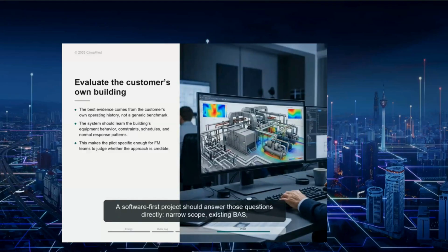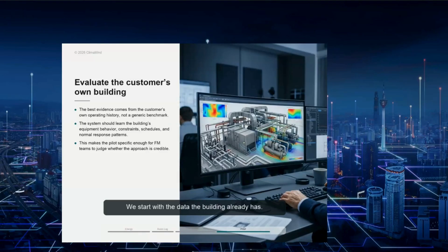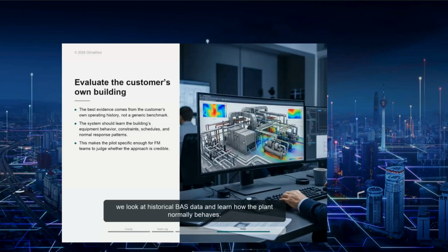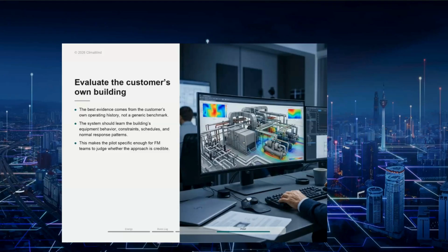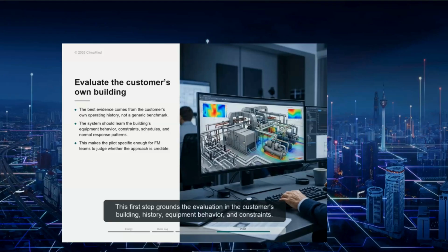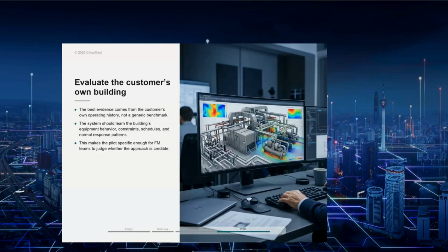Narrow scope, existing BAS, approved points and ranges, lighter installation, low tens of thousands cost, and results evaluated quickly against real building data. We start with the data the building already has. Before controlling anything, we look at historical BAS data and learn how the plant normally behaves, when demand rises, when it falls, how the plant responds, and which operating ranges the team already considers acceptable. This first step grounds the evaluation in the customer's building, history, equipment behavior, and constraints.